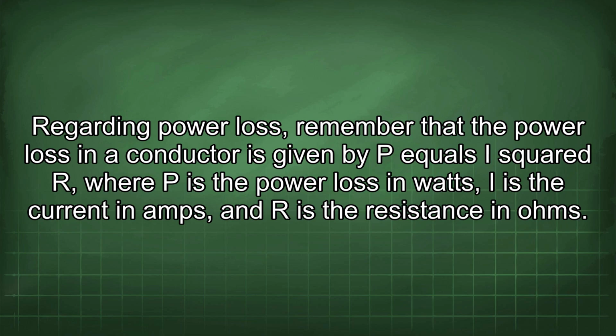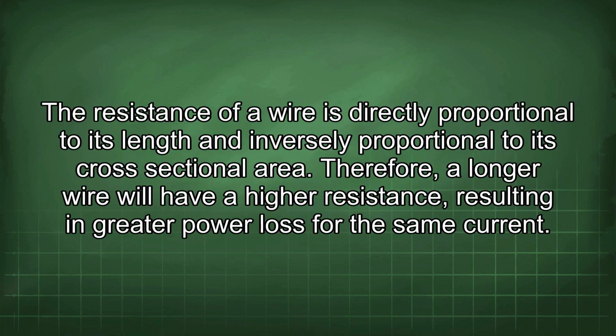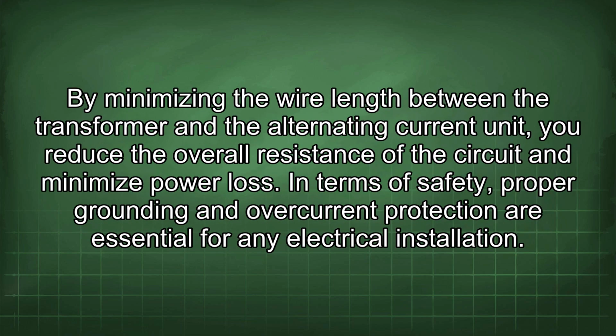Regarding power loss, remember that the power loss in a conductor is given by P equals I squared R, where P is the power loss in watts, I is the current in amps, and R is the resistance in ohms. The resistance of a wire is directly proportional to its length and inversely proportional to its cross-sectional area. Therefore, a longer wire will have a higher resistance, resulting in greater power loss for the same current. By minimizing the wire length between the transformer and the alternating current unit, you reduce the overall resistance of the circuit and minimize power loss.